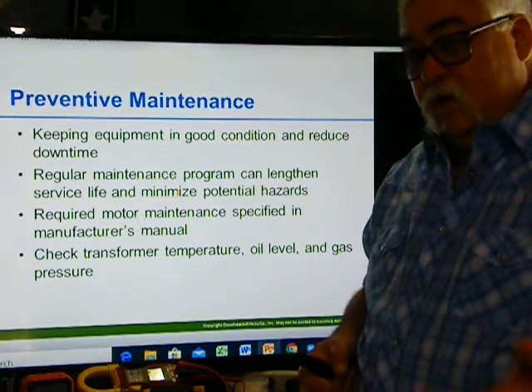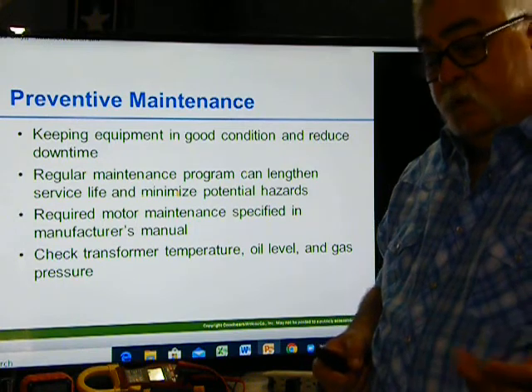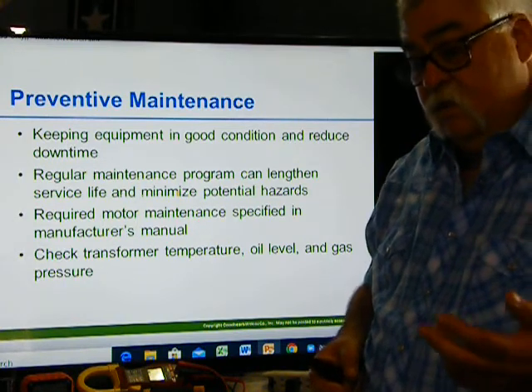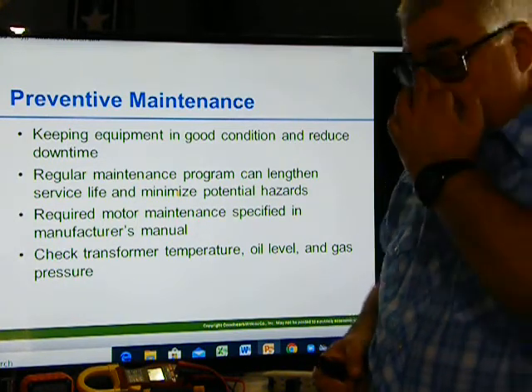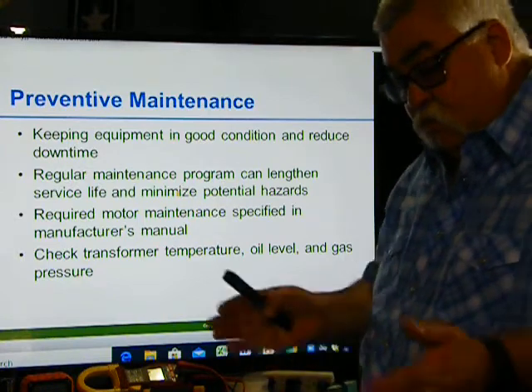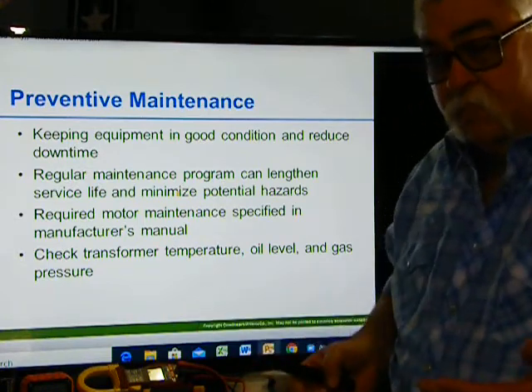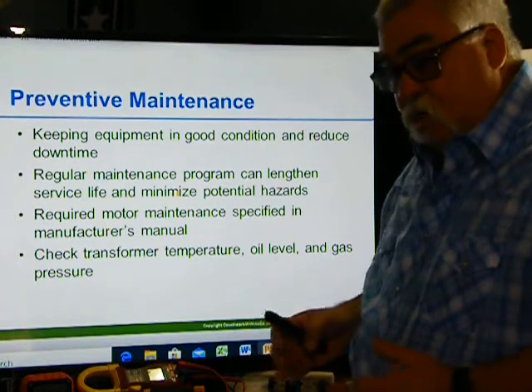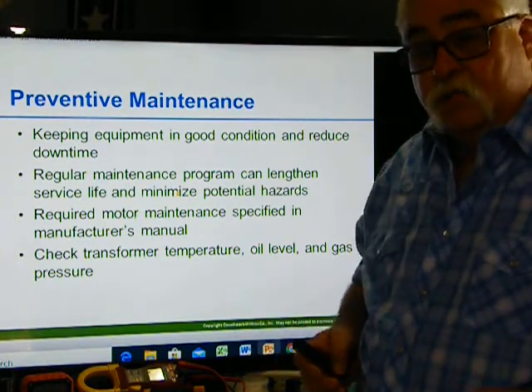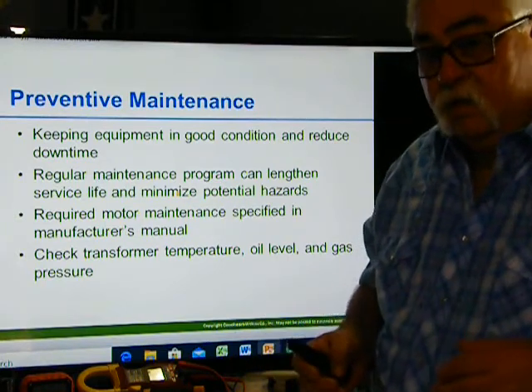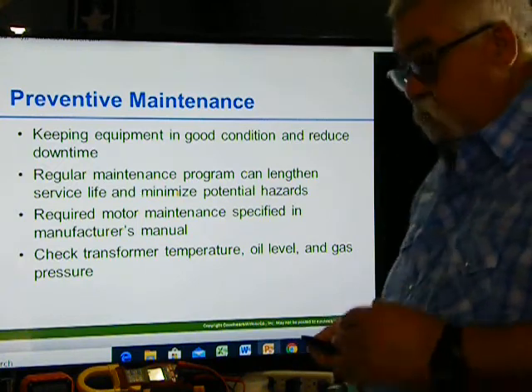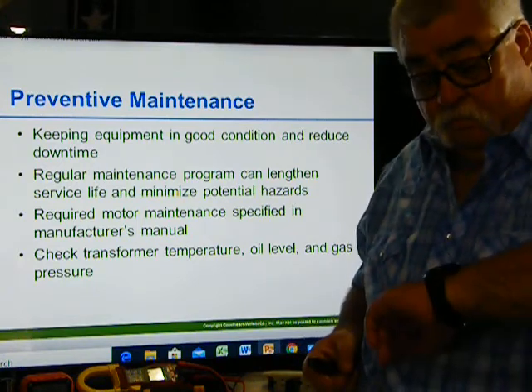It was sized at about 90% of its limit, so that could have been some of the cause for the extra heat too. But the transformer went bad. So when we went back, we changed it. We moved the transformer forward. The transformer was only about 1.5 years old. So we moved the transformer forward and we increased the size on it to bring it back down around 70%. But make sure your transformer is not overloaded.